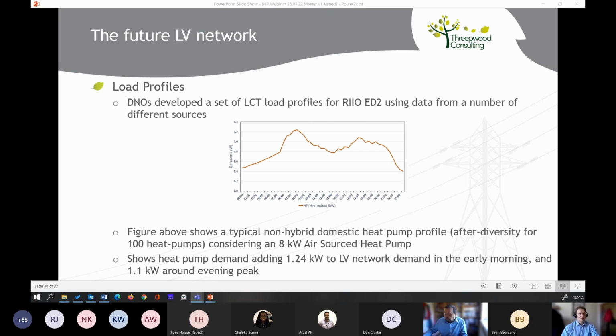Just to clarify, that is the average demand across a large group of consumers. Individually, maximum demand is a different consideration - that's where you're determining what the maximum demand is if they switch on that heat pump and it's doing maximum output. This is an averaged figure.